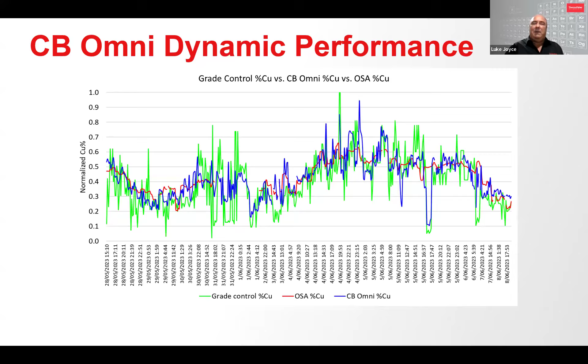So the considerations I've talked about up to now relate to the process variables on site that a PGNAA supplier can't generally control. However, there are considerations that can be controlled and that do impact the value a PGNAA analyzer can provide. One thing the manufacturer can control is the neutron source output capacity. Ultimately, it boils down to this: for an analyzer designed to accommodate a larger neutron output, you'll get more gamma rays generated, and the more gamma rays you generate, the better the precision you can achieve.